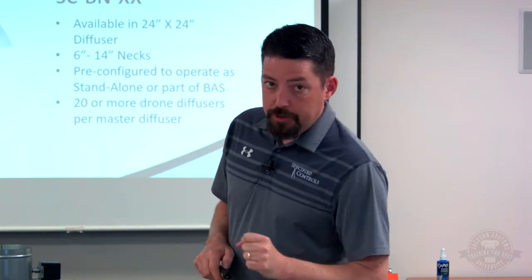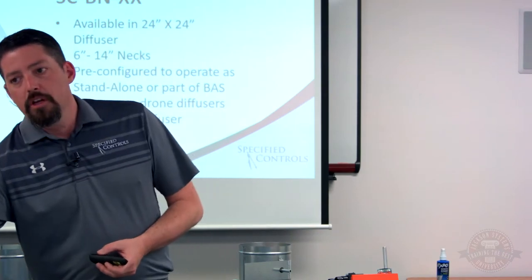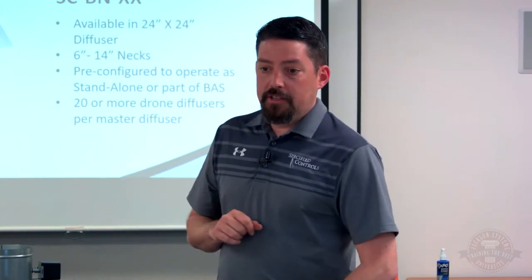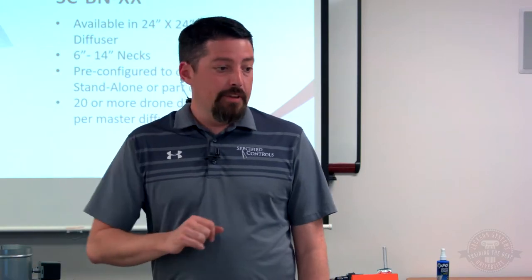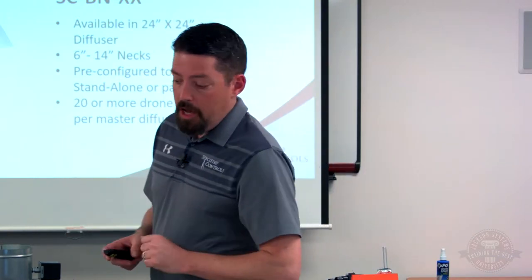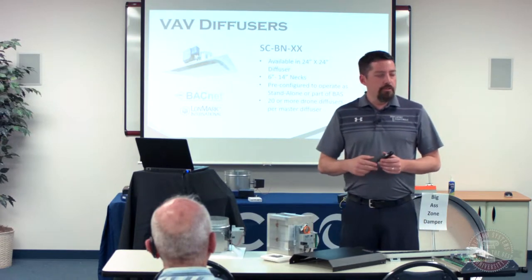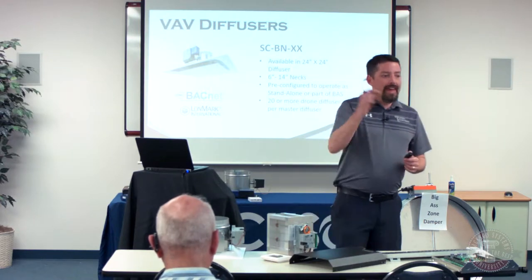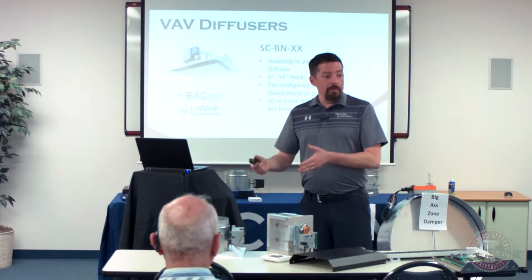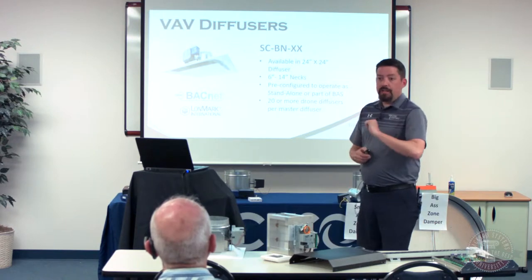Last topic from Mike: BACnet VAV diffusers. For commercial contractors dealing with building automation systems, we can make the VAV diffuser a BACnet device — monitored, controlled, and adjusted through the BAS. It's treated exactly like a VAV box in a building automation system; we're just not measuring flow. Five years ago, 95% of VAV diffusers sold were non-communicating. Last year, almost 40% of the VAV diffusers we sold were BACnet — it's becoming standard. BACnet devices can be daisy-chained as well.